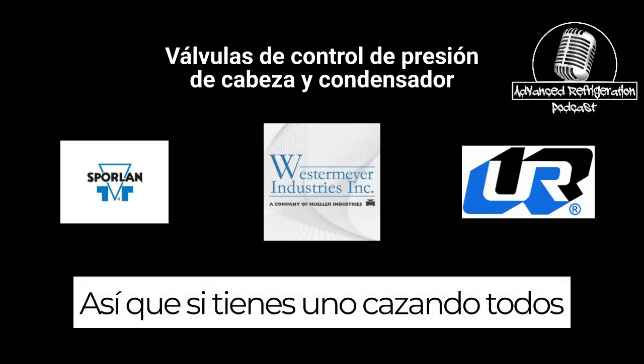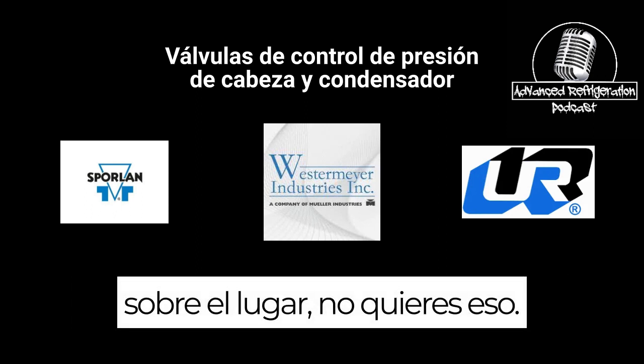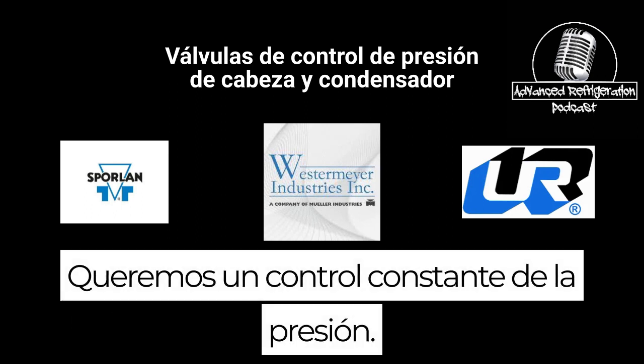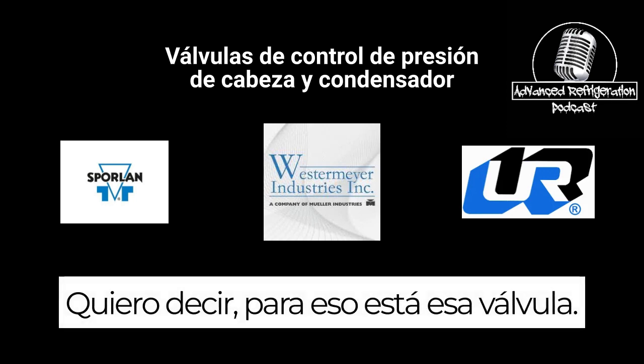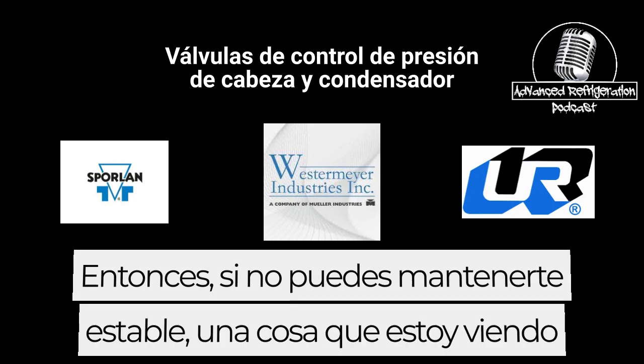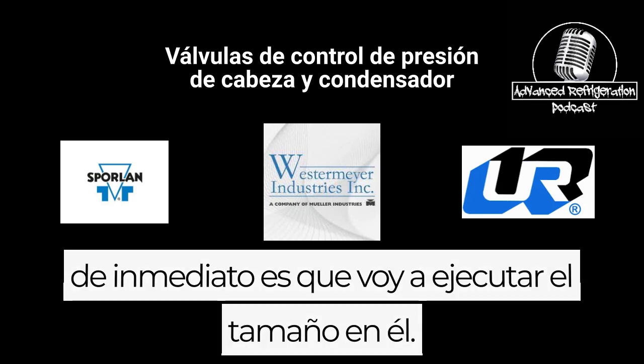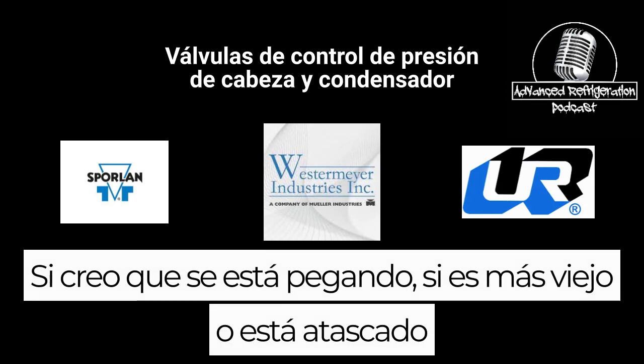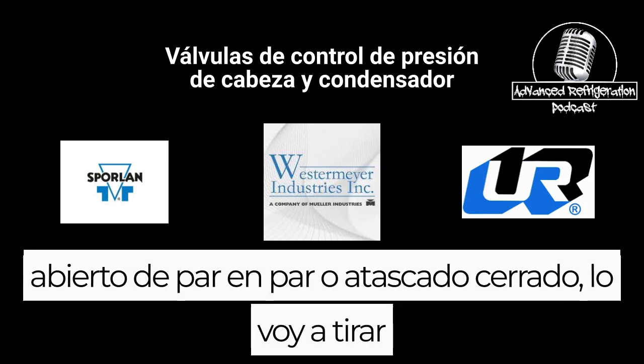And so if you have one hunting all over the place, you don't want that. We want steady pressure control. That's what that valve's for. So if it can't maintain steady, one thing I'm looking at right away is I'm going to run the sizing on it. If I think it's sticking, if it's older or stuck wide open or stuck closed, maybe doing nothing, I'm going to pull it apart and see.